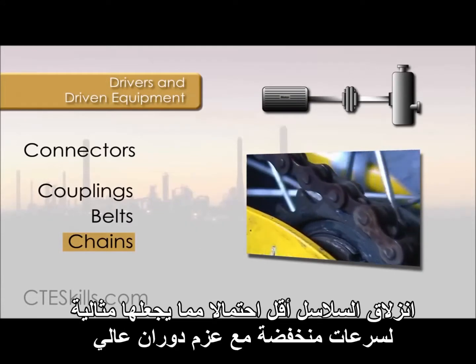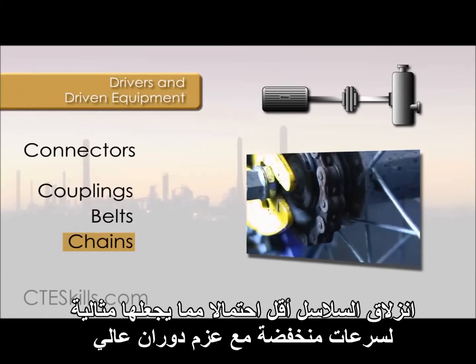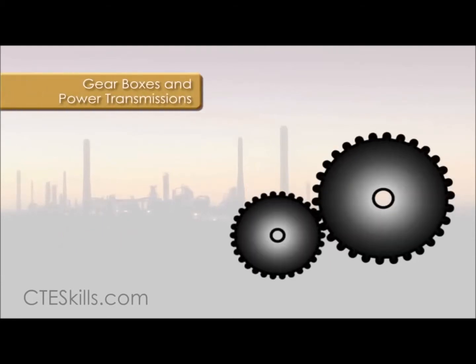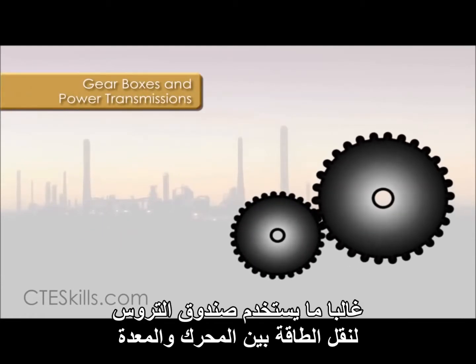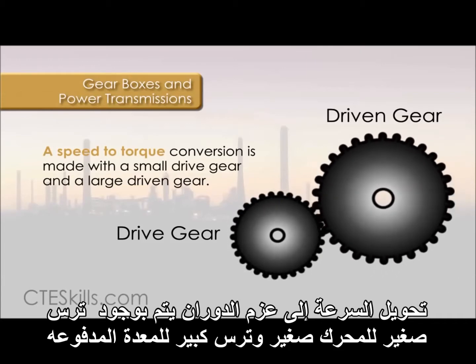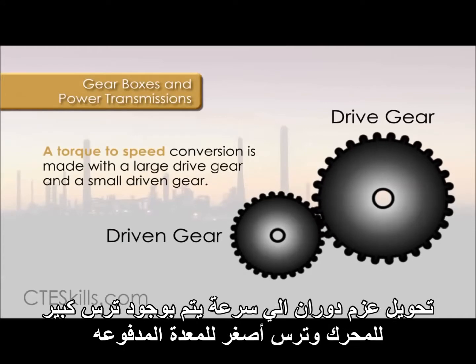With chains, slippage is less likely, which makes them ideal for low speeds and high torque. A gearbox is often used to transmit power between the driver and the driven equipment. A speed to torque conversion is made with a small drive gear and a large driven gear. A torque to speed exchange would be done with a large drive gear and a smaller driven gear.